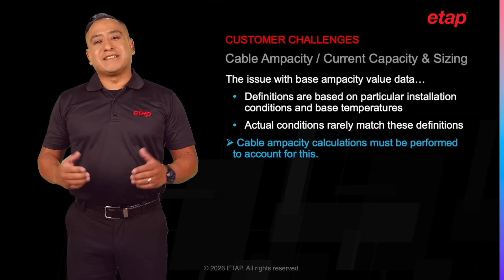Cable manufacturers and standards define base ampacity values, which are based on particular installation conditions and specific to base temperatures. However, these installation conditions rarely reflect the actual installation and operating conditions of the cable. As a result, cable ampacity calculations need to be performed to account for such differences. The differences can be accounted for through a full thermal analysis or through the use of adjustment or correction factors. These factors are valuable as they help calculate the maximum allowable current.